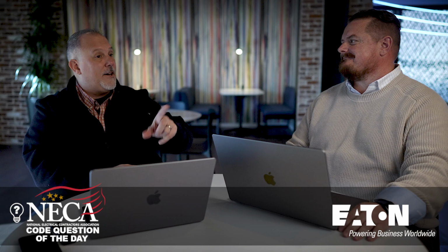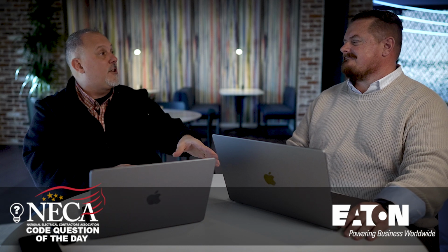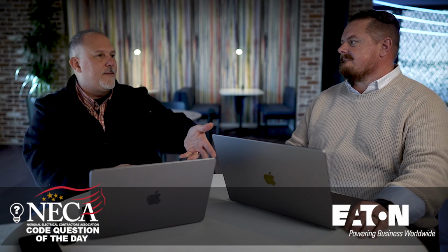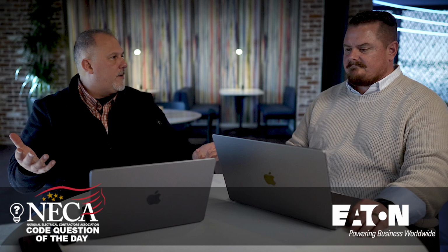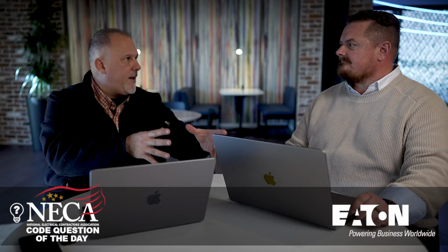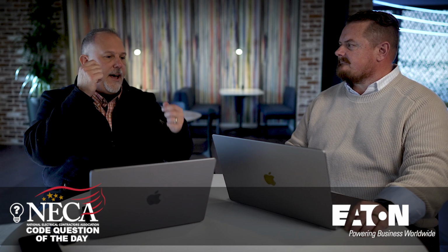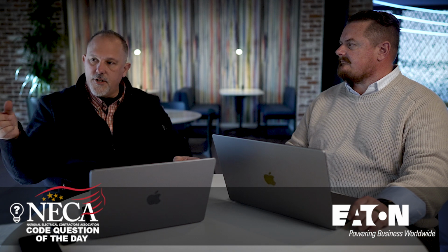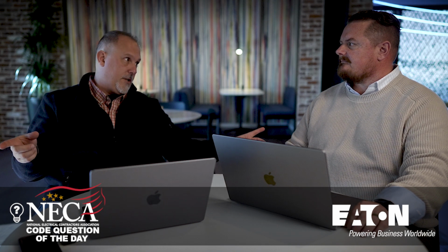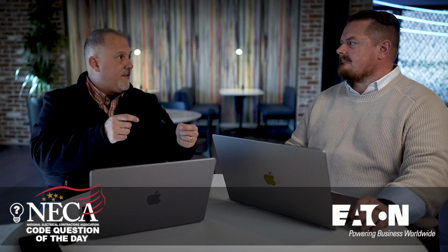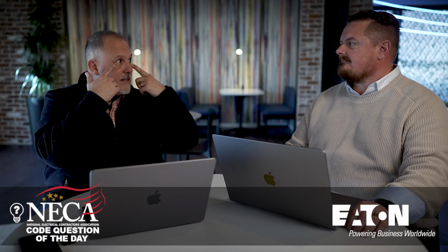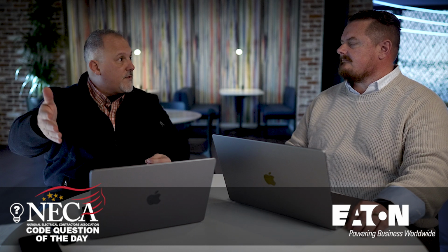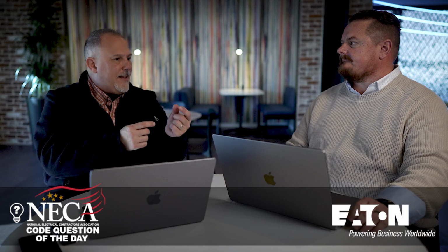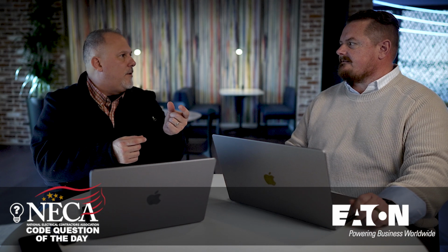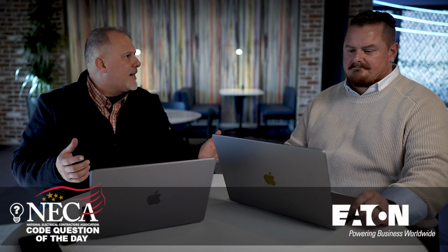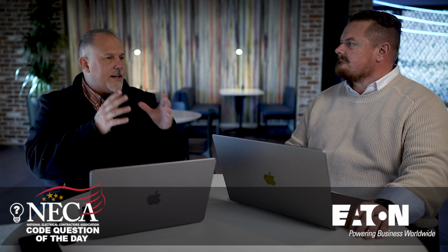And what I did was I calculated the incident energy at that equipment. And it was like 0.3 or something, right? So if I was going to work on that equipment and have a fault in that equipment downstream of a fuse, doing justified energized work, if I had a fault, I'm in gloves, glasses. If I followed the rules of 70E with that low of an incident energy, the arc flash boundary was less than the working distance. Right? Yeah, exactly. So it was really short. So I could get away with a pair of gloves.